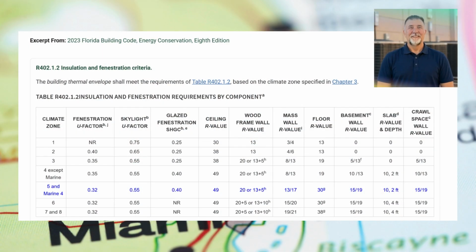Now, a lot of your building departments, when you build a new house, their codes are all on the websites. We talked about the building department websites and where to go and look at what the codes are for your state and location. That'll tell you whether, like in Florida, if the window is not an impact rated window, the prescriptive code states, and this is climate zone 2, that the window must have a 0.4 U factor and must have a 0.25 solar heat gain coefficient.